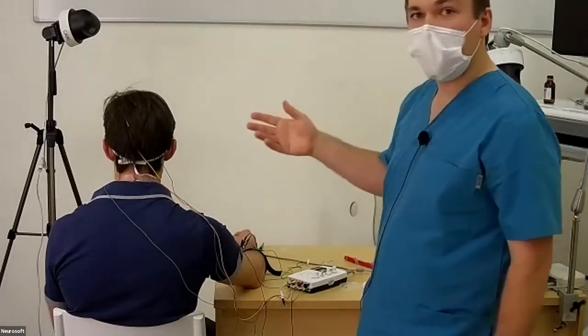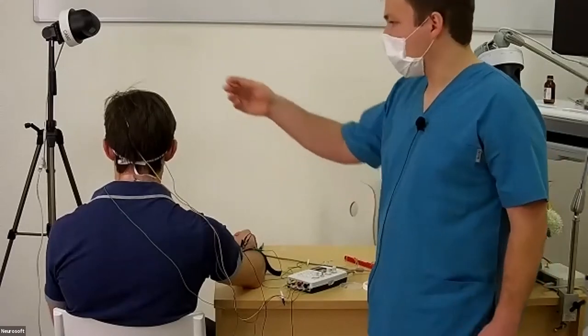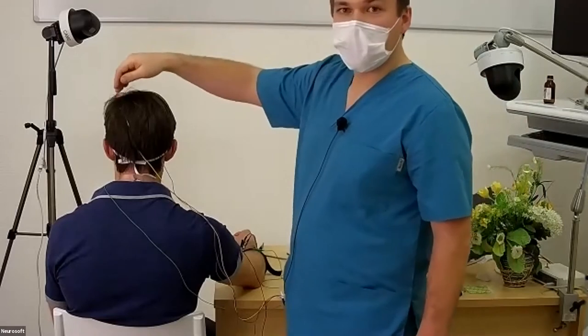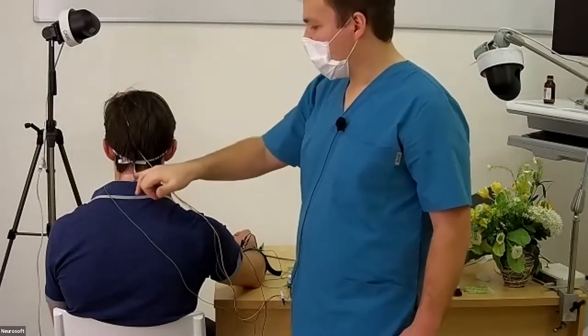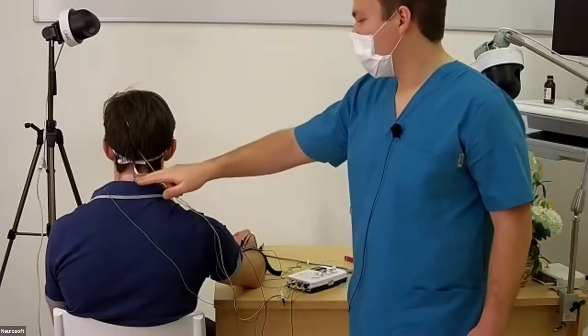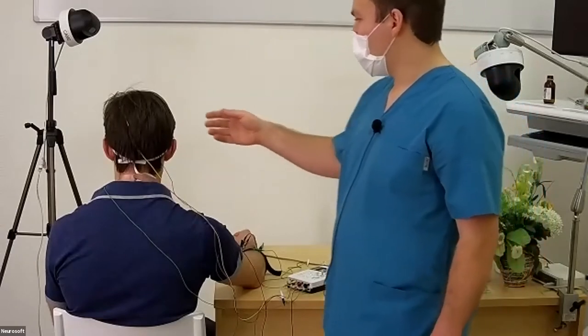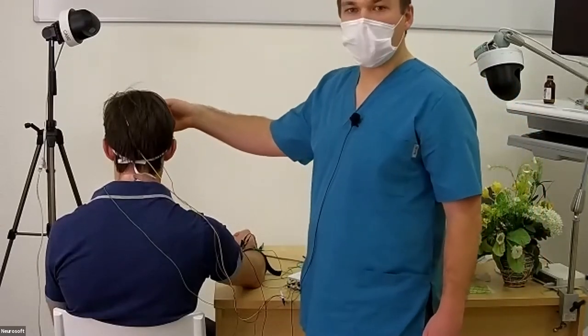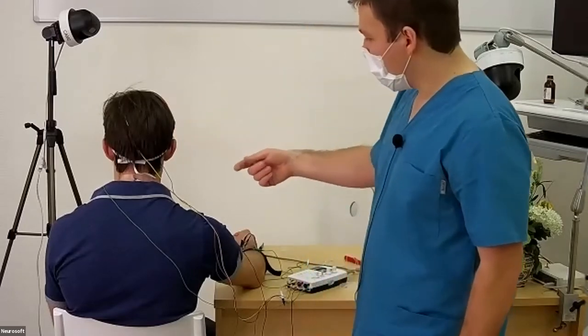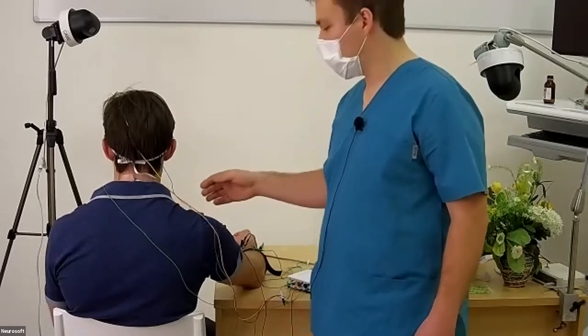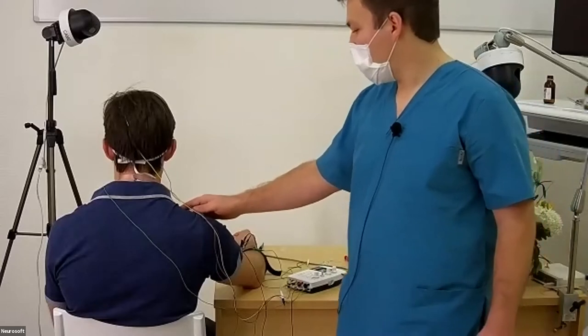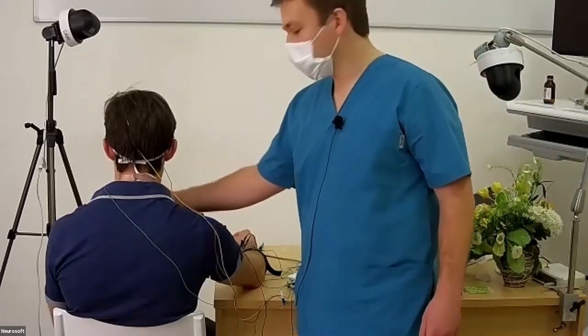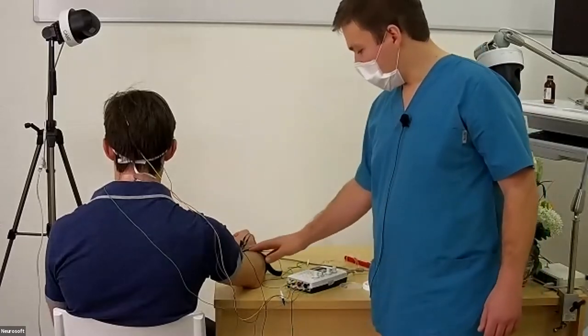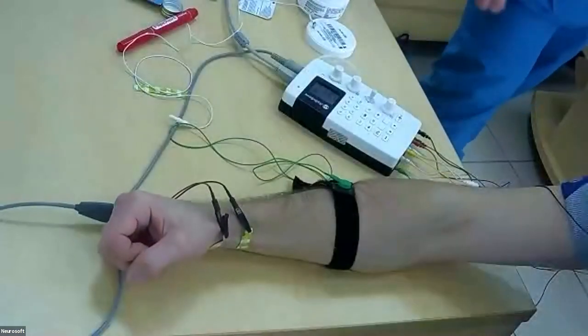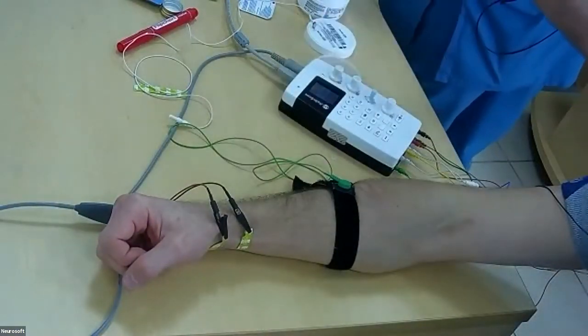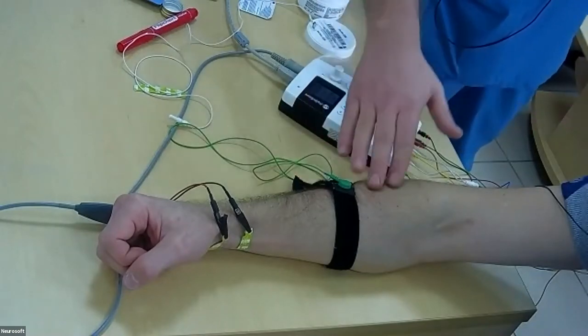This time we register somatosensory evoked potentials from the median nerve. We set the contralateral primary sensory cortex and the spinal level, and both of these channels register to the reference Fz electrode. We also register the peripheral nerve, ipsilateral Erb's point to contralateral Erb's point. We also need a ground electrode. Usually it must be set between stimulation and registration channels, for example, on the arm.